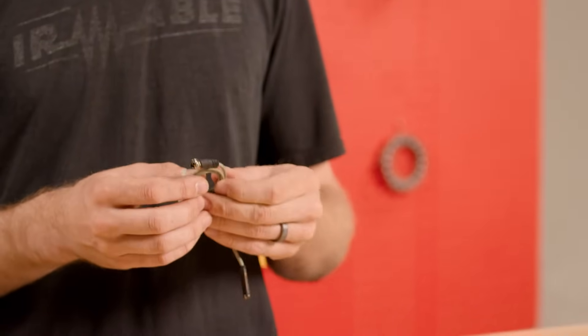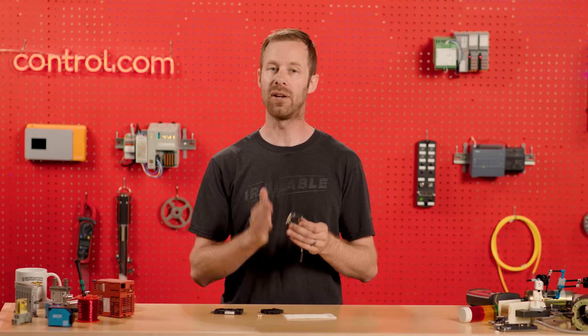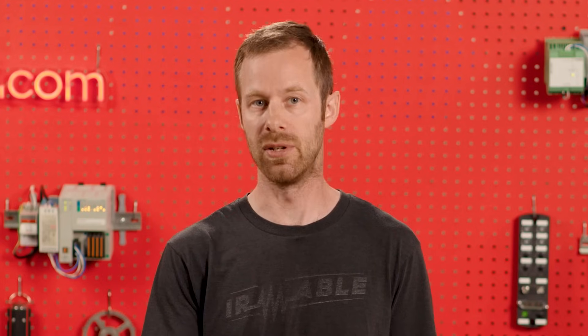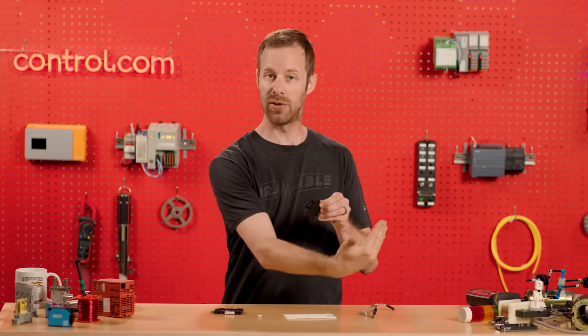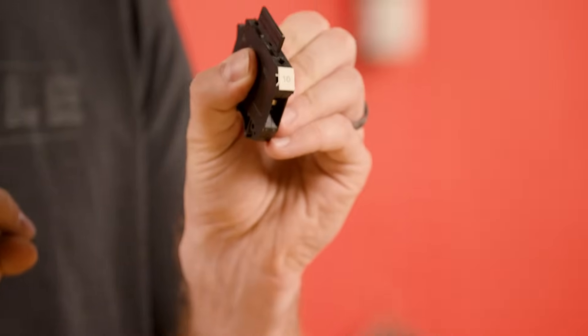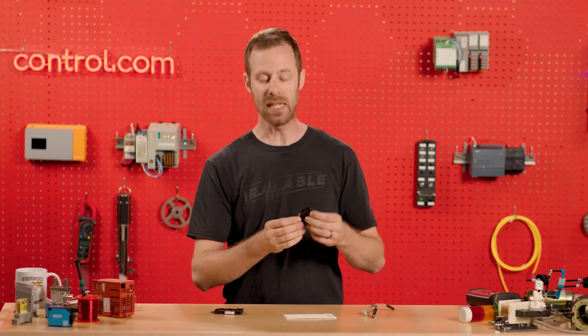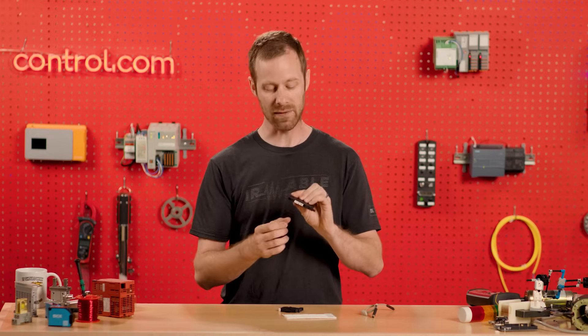We can sometimes even print directly on the cable itself — that's often the way you'll find it coming from a manufacturer. For example, if you've ever rewired a three-phase motor, very often the wires themselves have the wire T-numbers labeled directly on them. For terminal blocks, there's nowhere to zip tie a connector and nowhere to stick a label because the sides of the terminal block will be covered up by other terminal blocks next to it. So instead, special terminal block labels can be clipped right to the front, whether you're looking down at a control cabinet or looking up at it.